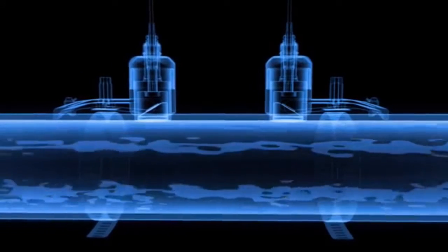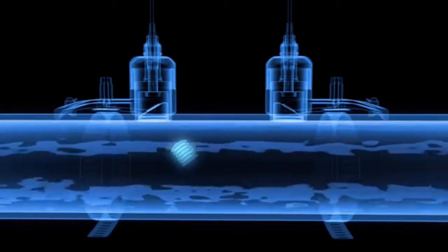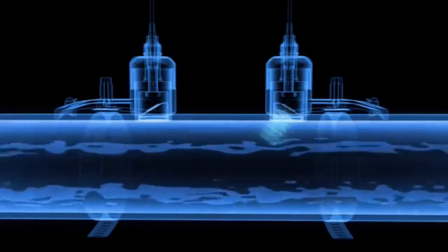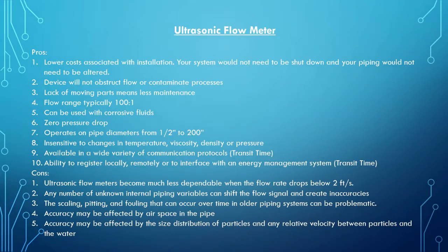Next up, we will discuss the pros and cons of ultrasonic flow meters. Starting with the pros, there are much lower costs associated with installation, as your system would not need to be shut down and your piping would not need to be altered. The device will not obstruct flow or contaminate processes. The lack of moving parts means less maintenance. The flow range is typically 100 to 1. It can be used with corrosive fluids. There is almost zero pressure drop.